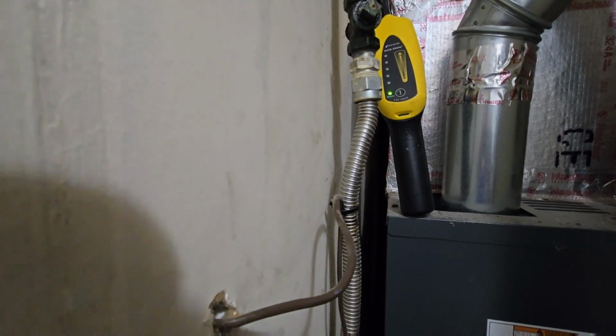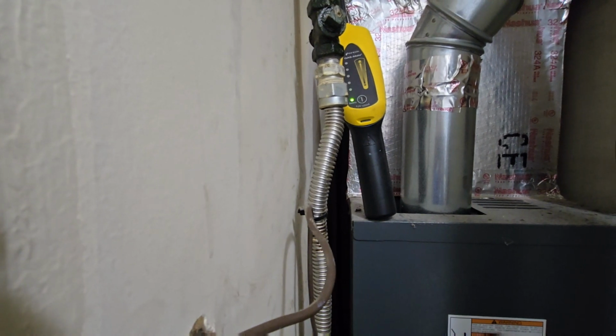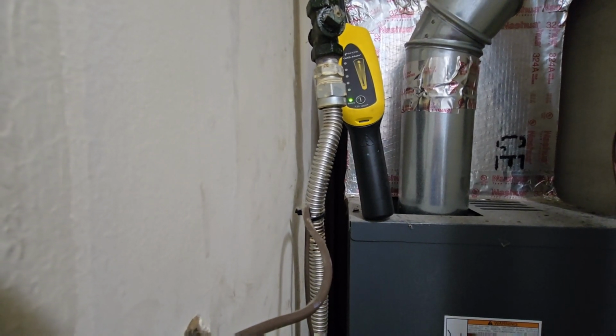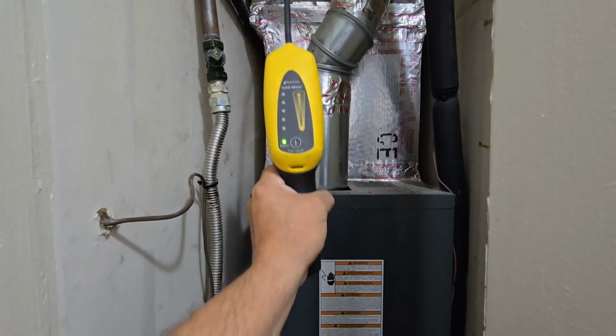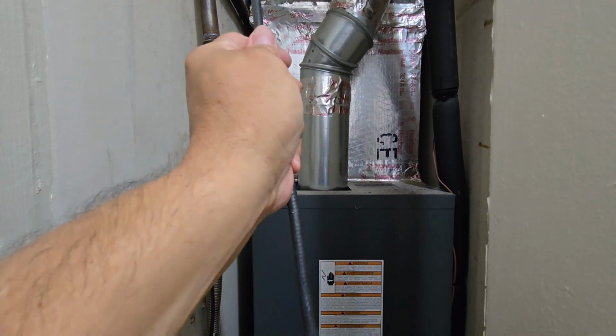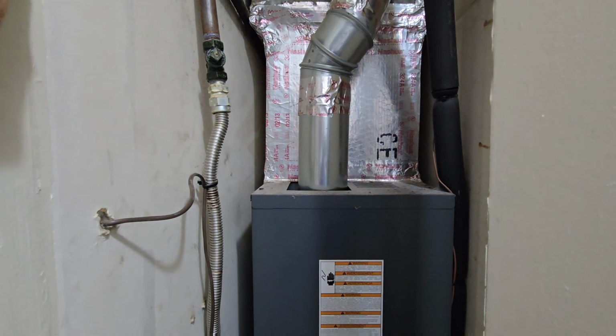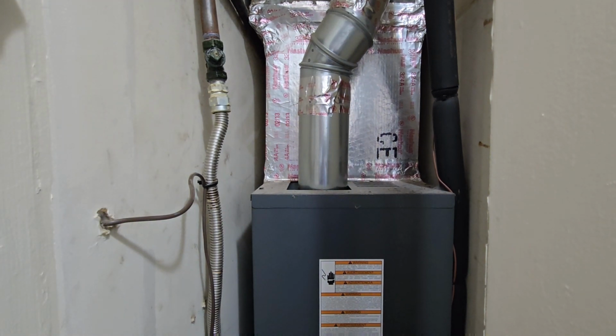I'm going to shut it off. We'll splice the video together in Video Magic, and then go from there. The only reason I wanted you to see the bulk of stuff, so you can see how we're testing the line. That's telling me it's picking up a leak. We're going to start from the bottom, coming out of the furnace with the black iron pipe.